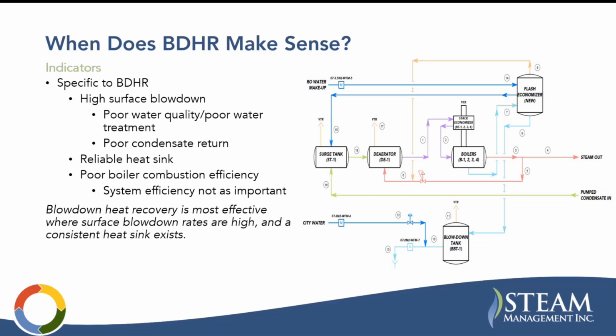You want to have a reliable heat sink. If they're using an atmospheric feed water tank, there's nowhere to grab the steam. Maybe they have an irregular way of controlling their makeup. It might just be too complicated. But if it's a standard boiler plant, a lot of times you're going to be able to put that heat somewhere. If you have poor boiler combustion efficiency, that's actually good for this, as with a lot of energy conservation measures. The less efficient the boiler is, the more fuel per amount of steam is saved. So if that makes sense. System efficiency is not as important because we're conserving all of our energy here within the boiler plant. So it doesn't really affect steam out and condensate back as much. We're offsetting this steam flow right here.